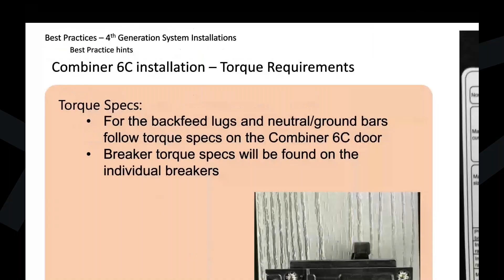I know, Jarrett, you're saying you live in an area where when an inspector comes out, they make you torque several of them to prove that they're right. Is that right? Yeah, absolutely. It's been starting in the Central Valley as of a couple years ago. At inspection, the inspectors will have an installer out there with them and require them to show a torque setting, so they torque it and use a paint pen to show that those are torqued.